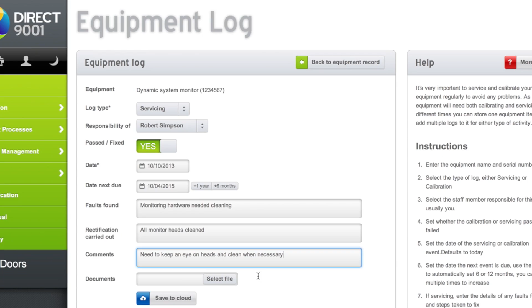If this is a servicing log, enter the details of any faults found and the steps taken to fix it. If this is a calibrating log, set the switches for information and certificates you now have to prove your equipment is calibrated. You can upload a document file to the log as proof of calibration.